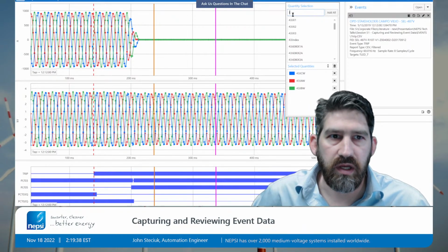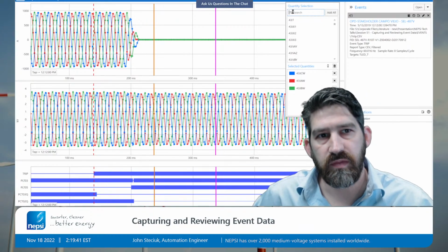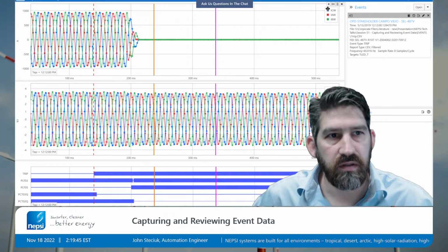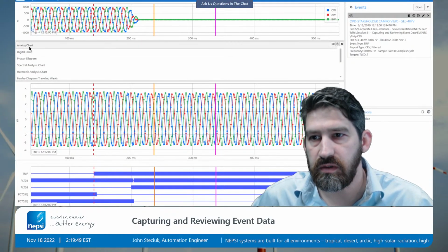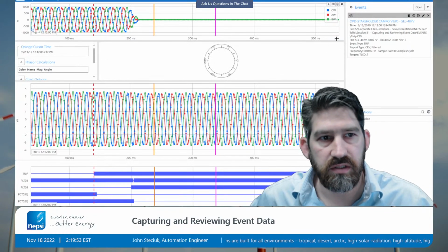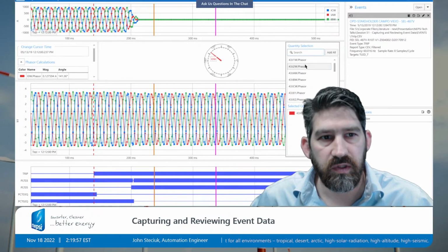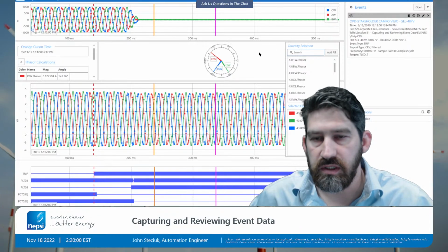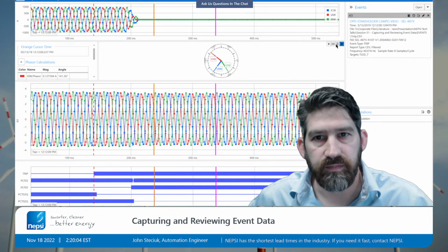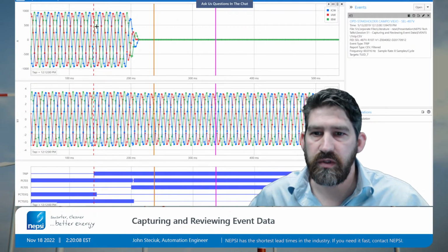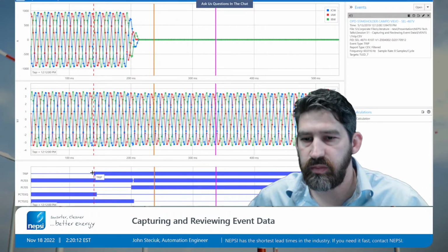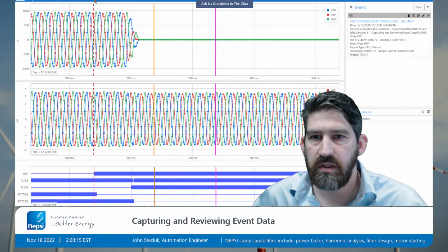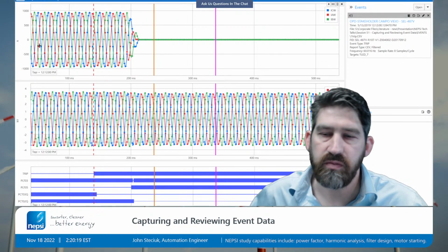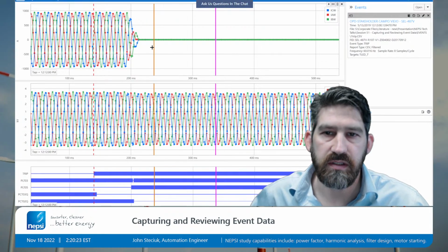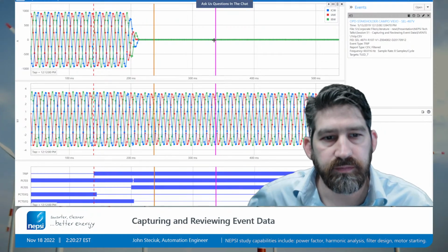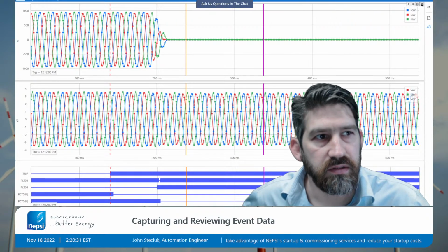And this software allows you to select different quantities and add different charts. I can add a chart that shows the frequency, or I can look at phasor diagrams and just add different data values here. So it's pretty cool software. You can play around with it, and there's a lot you can do. But you can see this event picked up where this red line is, and the trip bit asserts at this point. So we've got several cycles of pre-fault data, and you can see the current shut off when the equipment does. So not much going on in this event, but let's take a look at another one.